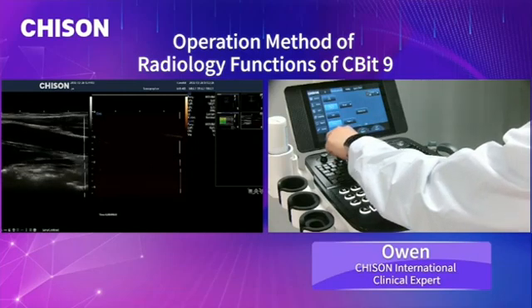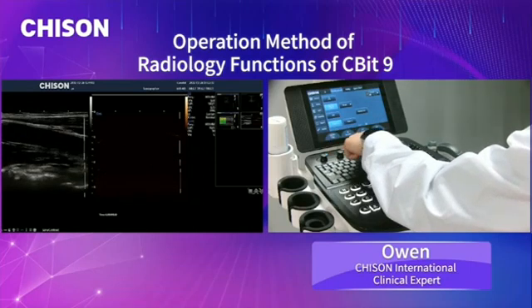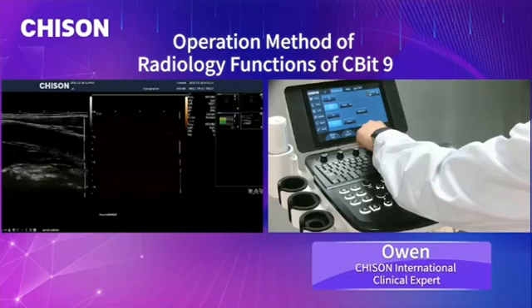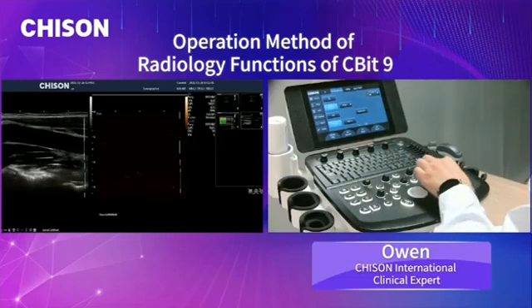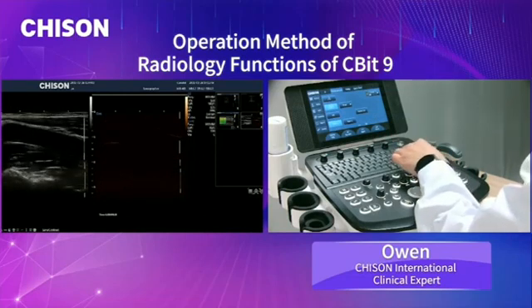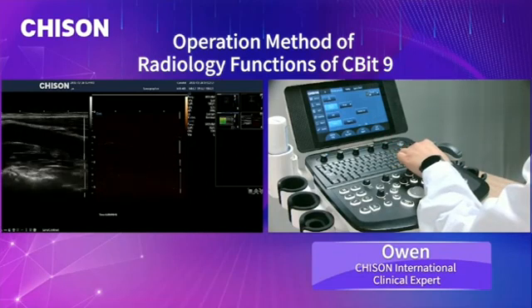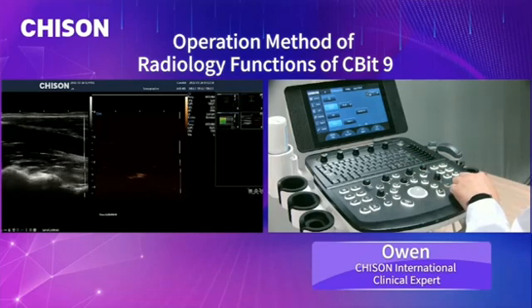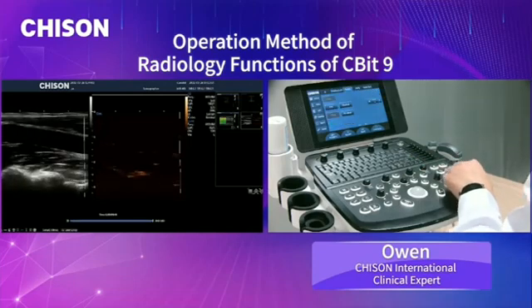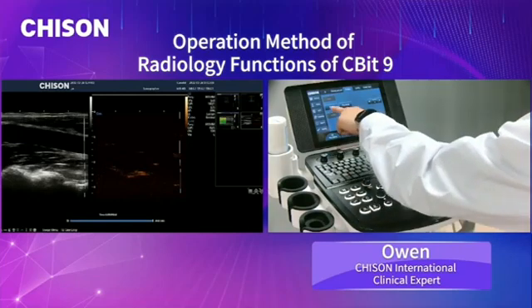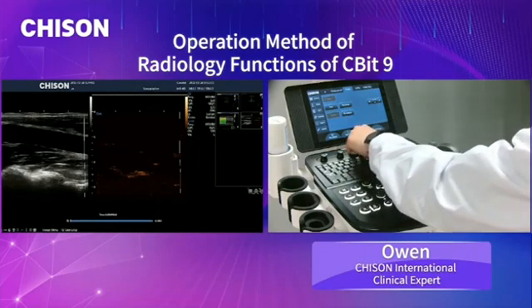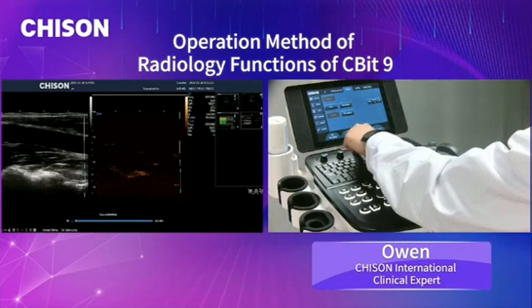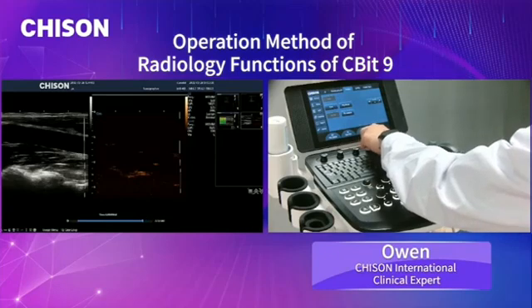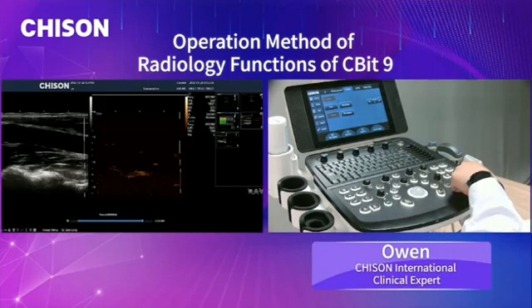For the frequency, we change the frequency to adjust the resolution and the penetration according to the real-time need. And we can press the depth button to change the scanning depth. And we can rotate the B button to change the total gain. Make sure that the gain of the contrast interface is not too low to show the entering of bubbles, and the gain is not too high to submerge micro bubbles during the early stage. Once you have finished your scanning, you can save your cine loops and set the start point and the end point. You rotate it to set the start frame and end frame, and press freeze to save the cine loop.